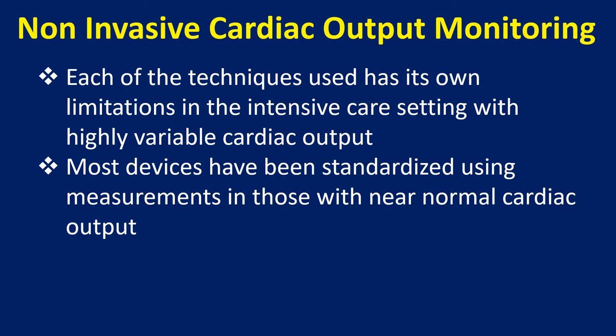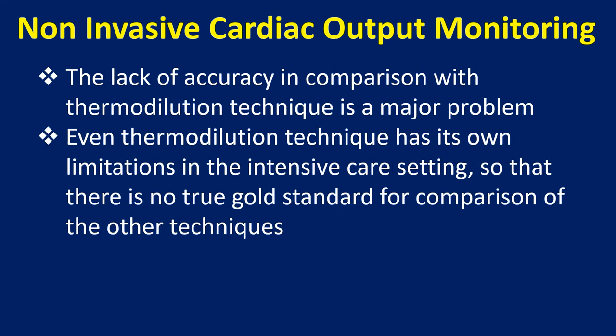Each of the techniques has its own limitations in the intensive care setting with highly variable cardiac output. Most devices have been standardized using measurements in those with near-normal cardiac output, and the lack of accuracy in comparison with thermodilution is a major problem. Even thermodilution has its own limitations, so there is no true gold standard for comparison.